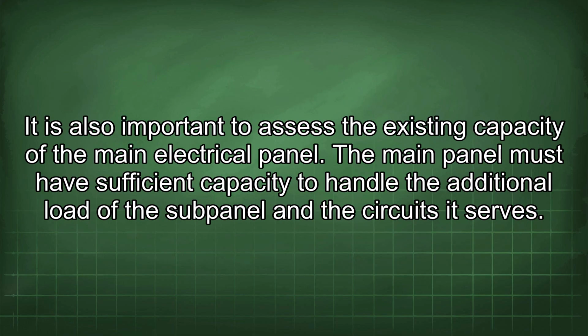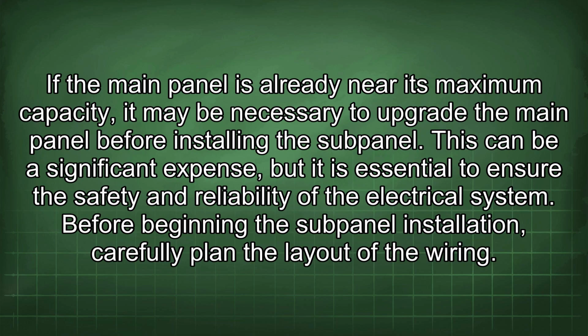It is also important to assess the existing capacity of the main electrical panel. The main panel must have sufficient capacity to handle the additional load of the subpanel and the circuits it serves. If the main panel is already near its maximum capacity, it may be necessary to upgrade the main panel before installing the subpanel. This can be a significant expense, but it is essential to ensure the safety and reliability of the electrical system.